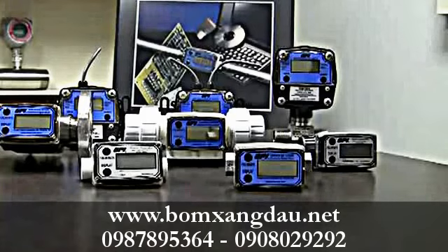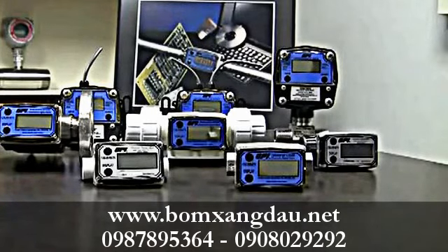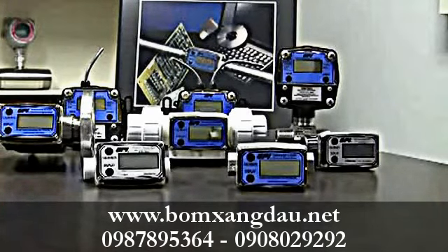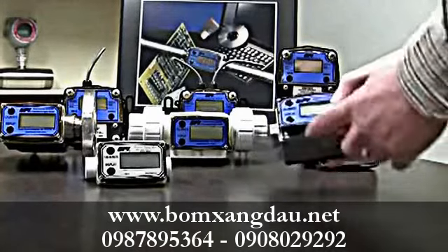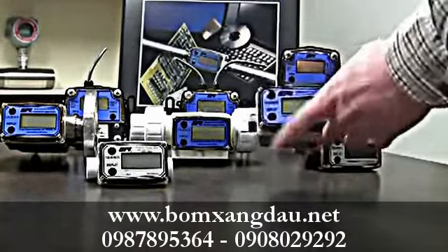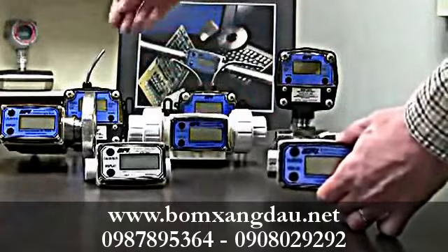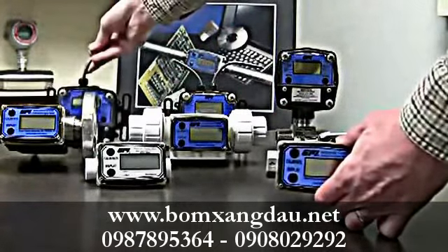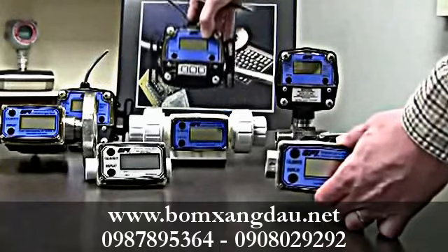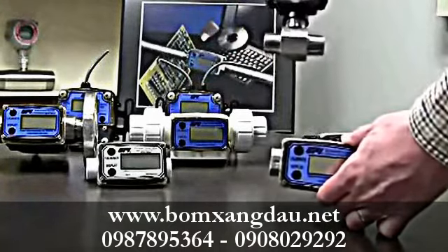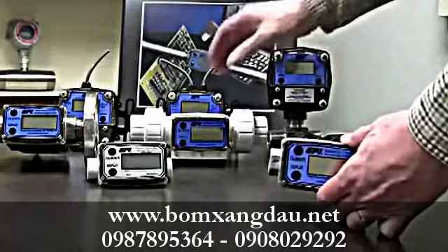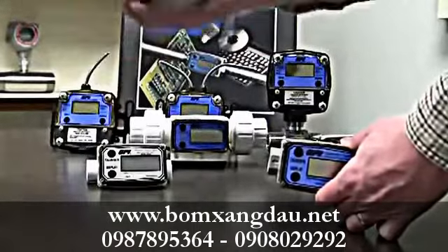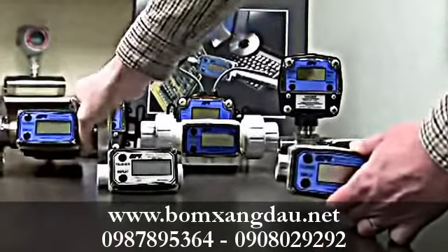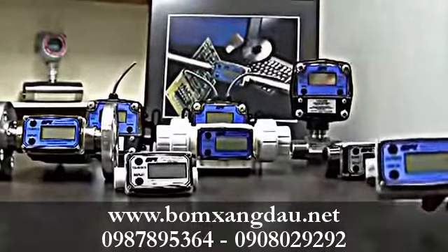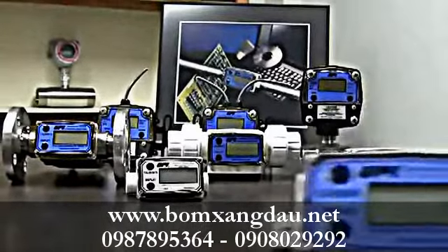Today we're talking about how to calibrate a meter. As you can see, we've got tons of different meters, but the displays on all of them look pretty much alike. You can kind of tell because they all have two buttons, a display button and a calibrate button. You can see different colors, remote displays, displays with 4 to 20s, displays on top of meters, displays on the front, or displays with 4 to 20s out the back. But they all have the same display on the meter. Now today we're going to take a look at this meter and see how to calibrate it.